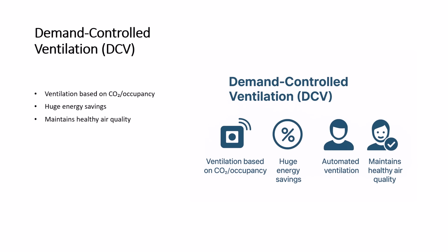Next we'll talk about DCVs, demand controlled ventilation, in our building. Ventilation depends on the carbon dioxide volume in our space and the occupancy level. If we have more occupants, more oxygen will be required to maintain good air for everyone's breathing, so CO2 should be removed and fresh oxygen added. Then there's the factor of energy saving - with DCVs we can enhance energy efficiency of our areas.